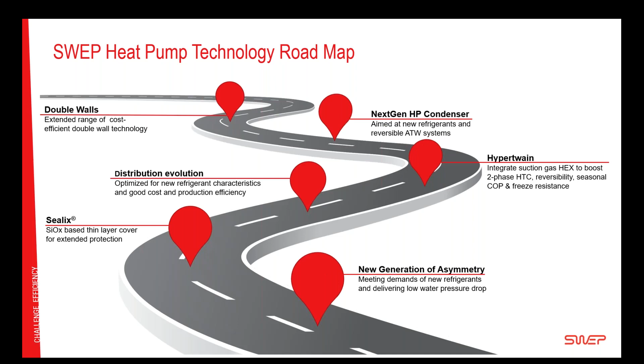Here, just to quickly give you an overview to set the frame going forward, this is the platform we have for heat pumps. Depending on what capacities, specifications and needs you have, we have a smaller range with a 4 size and 8 size, and then the medium range with a Q20, our new developments. We have the double wall, mainly within heat pumps due to the propane requirements that some choose to use. And then for more commercial sized heat pumps, we have the bigger sizes of the 250 AS. So basically all these function very well with whatever refrigerant you choose to design with, and we manage working pressures up to 49 bar, which is the highest requirement for the R32. So this is just to set the frame that we have a big portfolio to cover all the different types of needs on the market.